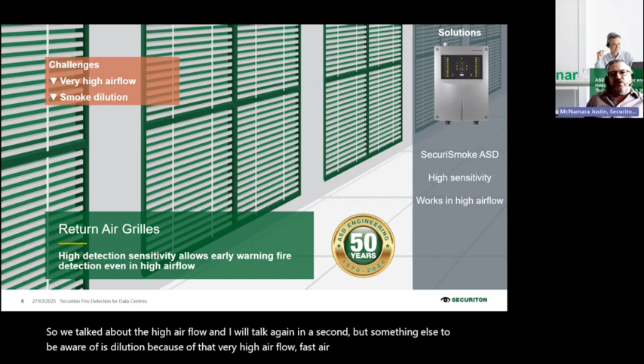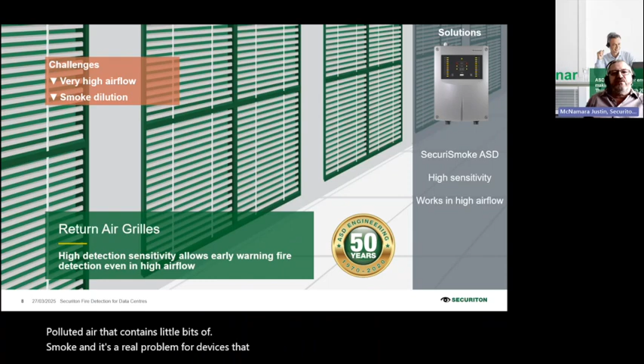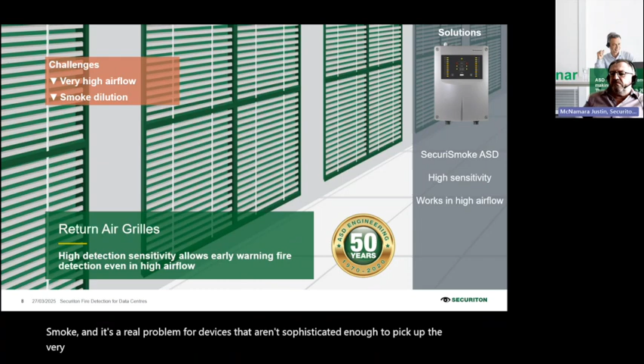So we talked about the high airflow, and something else to be aware of is dilution. Because of that very high airflow, fast air movement, smoke - particularly in its very early stage - is diluted by all that high airflow. That potentially clean air just dilutes polluted air that contains little bits of smoke. It's a real problem for devices that aren't sophisticated enough to pick up the very small early bits of smoke.